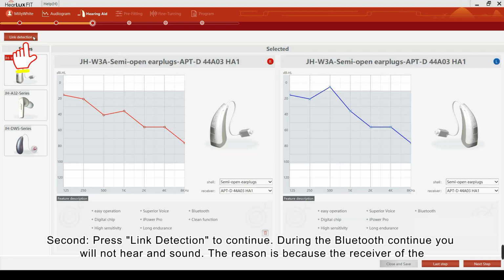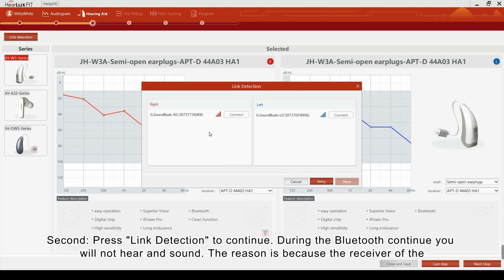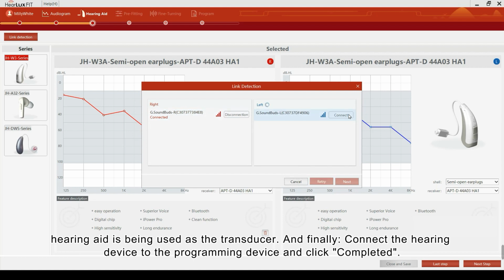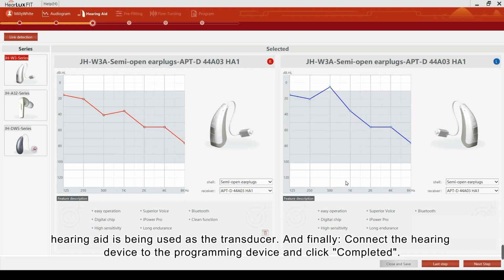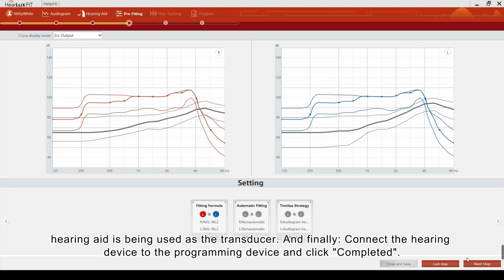Second, press Link Detection to continue. During the Bluetooth connection you will not hear any sound. The reason is that the receiver of the hearing aid is being used as the transducer. And finally, connect the hearing device to the programming device and click Completed.